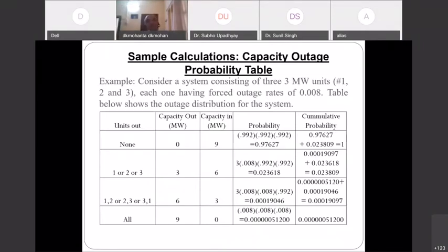Here the probability will be 0.008 for the one unit which has failed, and 0.992 for one surviving unit, and another 0.992 for the other surviving unit. Because there are 3 combinations, either unit 1 trips, or unit 2 trips, or unit 3 trips, that's why it is 3 times this one. I will use the nCr formula. This is the cumulative probability, I'll come to it later. These are the probabilities.